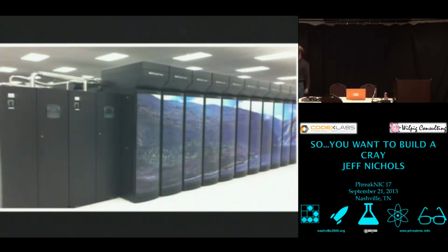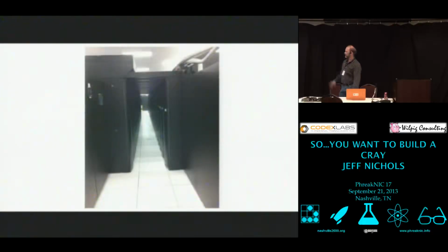On each of the machines, you'll see this machinery here on the left. We'll talk about that in a little bit, but that's really the refrigeration units for these things. That's looking down the corridors of these racks. You're seeing the back side of one rack and then the front side of the next rack going through. So there's not back rack and back rack? I don't think so. So they don't have cool and hot aisles? That's weird that they wouldn't have that. We do not.